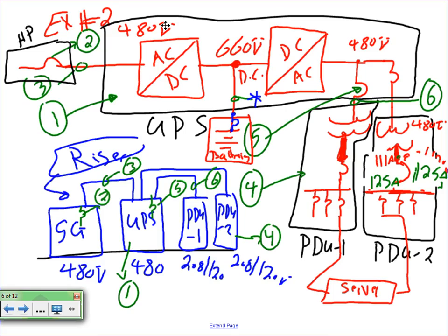It's like the fire alarm panel. Remember that fire alarm panel we were talking about yesterday? There are batteries there. If the power goes off, it alarms that the power went off, and it continues functioning for a predetermined amount of time. Same thing, except big batteries. Okay, any question about how the system is made together? Physically, how you put them together.